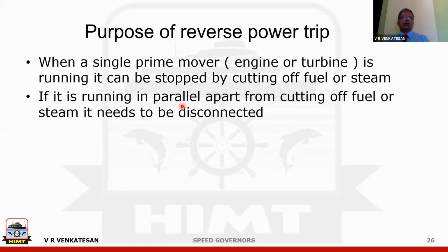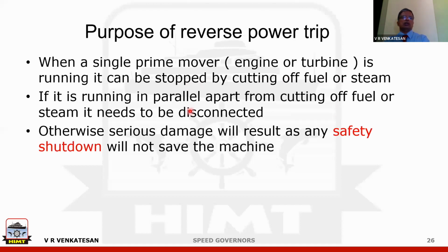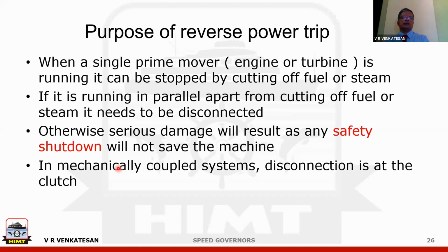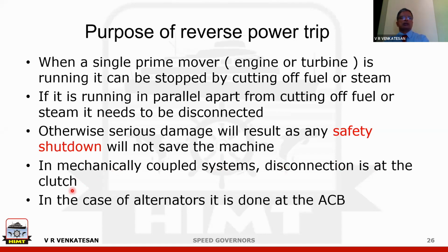Once again, to repeat: if a single prime mover is running, it can be stopped by cutting off fuel. If it is running in parallel, you have to disconnect. Otherwise, serious damage will result, as the safety shutdown will not save the machine. In a mechanically coupled system, disconnection is at the clutch. In the case of an alternator, it is done at the air circuit breaker. This is the easiest way to understand why reverse power protection is right.